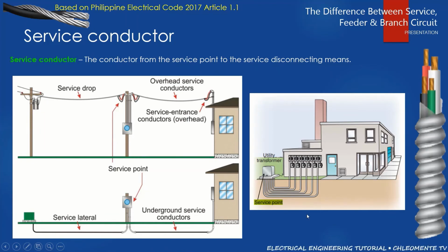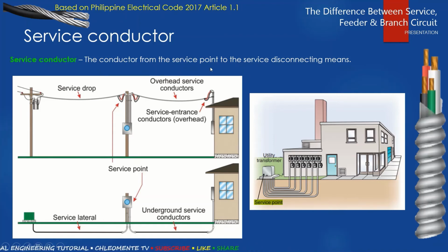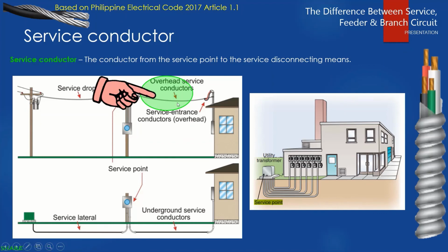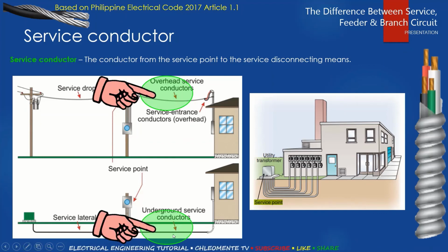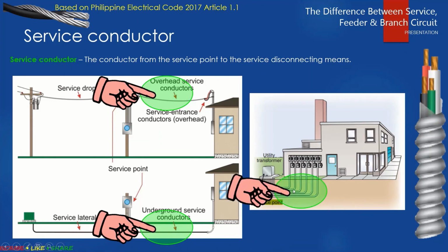Service conductor. So sa service conductor, is a conductor from the service point to the service disconnecting main. So any conductor between the service point, just kanina, at saka yung disconnecting main, tinatawag yan na service conductor. Papasok ng ating bahay na yan. So in this case, overhead service conductor. In this case, underground type of installation. So service conductors pa rin yan. And this one, so yan yung mga service conductor between the service point and the disconnecting mains or service equipment.